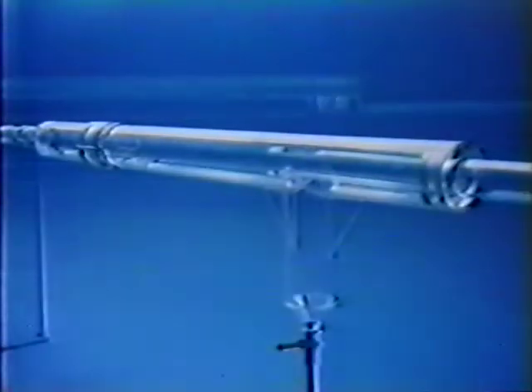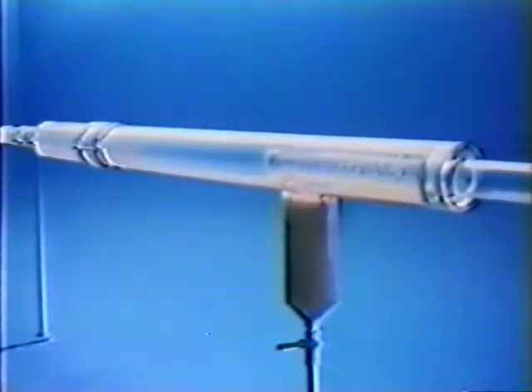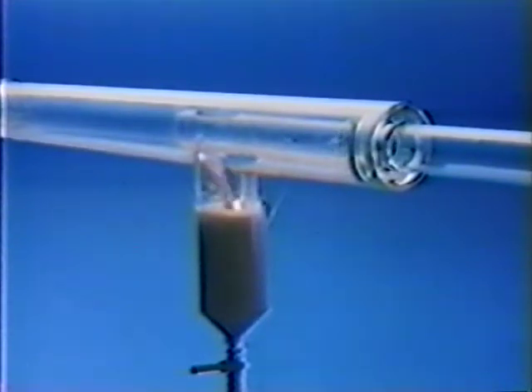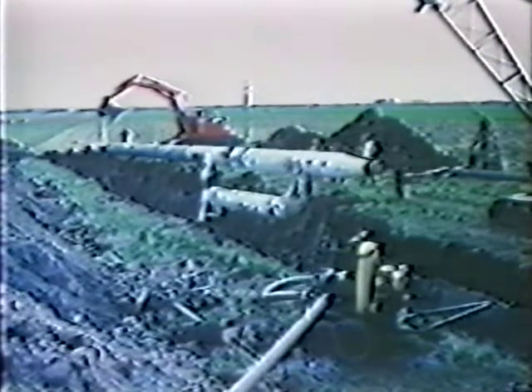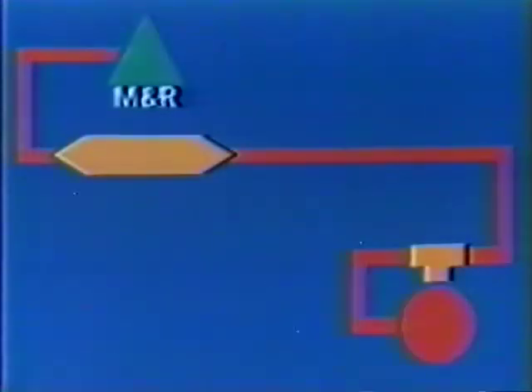The liquid receiver is also suitable for catching slugs. The blow-by is only slight. After a series of practical tests, 200 liquid receivers of this type were built into the regional pipelines downstream of all the measuring and regulating stations. Gas delivery stations are protected against condensate trouble by a liquid trap downstream of the measuring and regulating station and by a separator upstream of the delivery station.